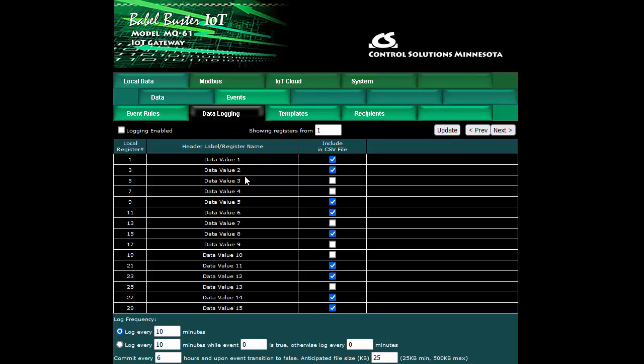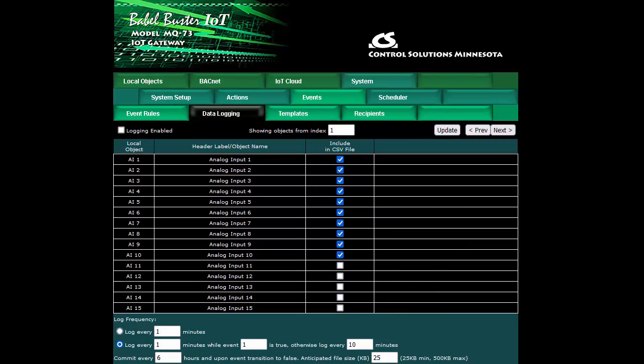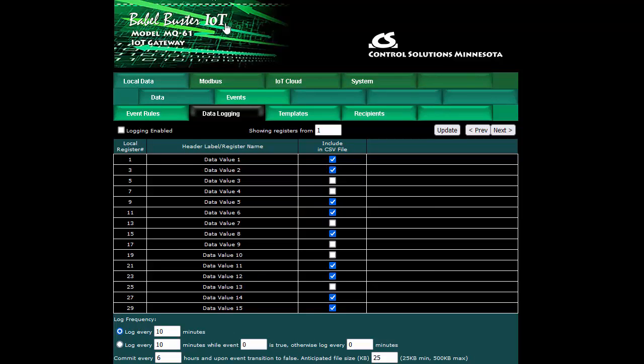In each case what you're going to end up with in the CSV file for a header line is the register name or in the case of BACnet the object name. From that point on each line will have a column for register or object and in each column there will be a data point which is logged every however many minutes you define at the bottom.